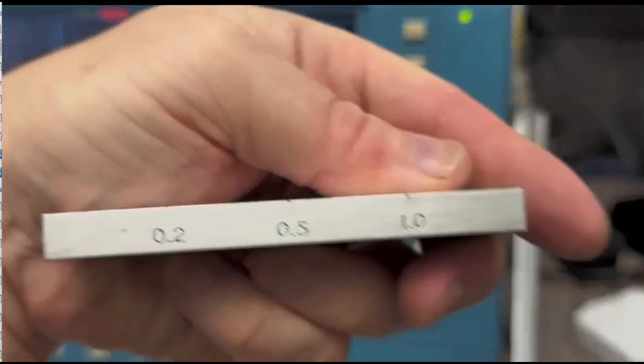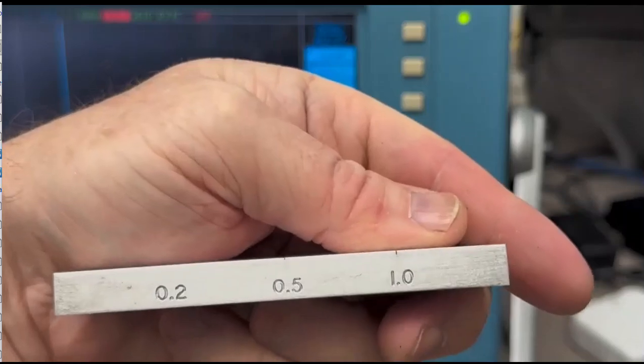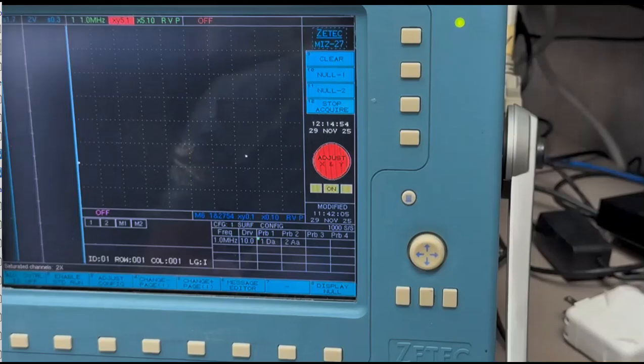Obviously millimeters because it's one millimeter deep on the right, half millimeter, and then 0.2 millimeters. Pretty small cracks, but we're looking for small cracks with eddy current, right? You don't even want a small crack on your airplane that you're flying on.